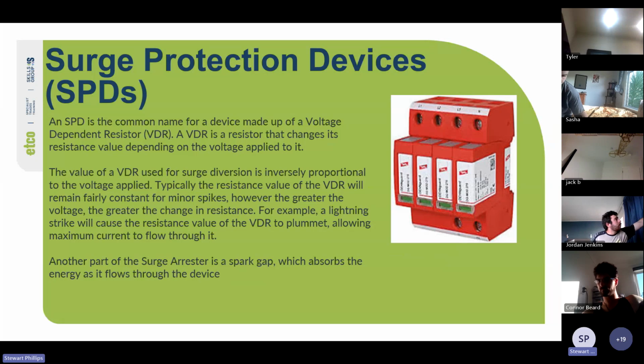Cool. So an SPD is the common name for a device made up of a voltage dependent resistor, or VDR. A VDR is a resistor that changes its resistance value depending on the voltage applied to it. The resistance of a VDR used for surge diversion is inversely related to the voltage applied. Typically the resistance value of the VDR will remain fairly constant for minor spikes. However, the greater the voltage, the greater the change in resistance. For example, a lightning strike will cause the resistance value of the VDR to plummet, allowing maximum current to flow through it. Another part of the surge arrestor is a spark gap, which absorbs the energy as it flows through the device.